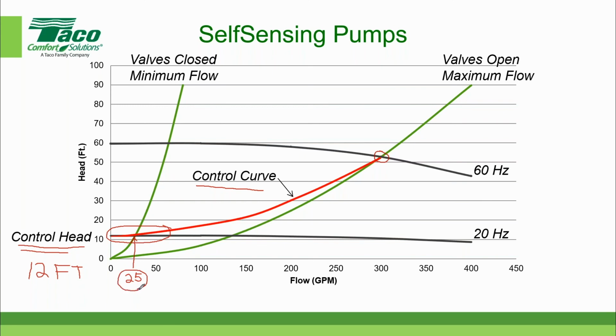Now, when it comes to calculations, nearly all of us calculate the pressure drop at the design flow, but very few of us ever calculate the pressure drop, the 12 feet, at minimum flow. In this case, the control head is essentially the same value as the pressure drop at minimum flow, 12 feet at minimum flow. Hopefully that helps, Brett. I think so.